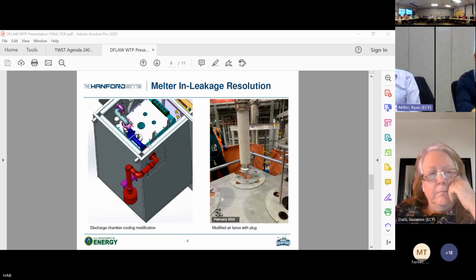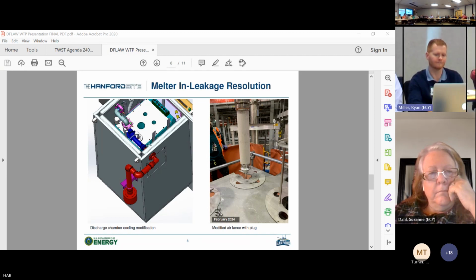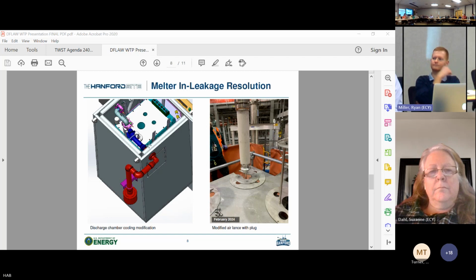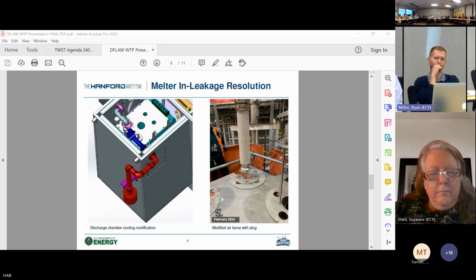The entire system, and I didn't highlight this, has a cascading ventilation system by law. You've got the gallery areas, the annulus area, and the plenum area. All of those are fully functioning. The only one that was in manual during this time frame was the off gas, which pulls the vacuum on the plenum. All the others have been operated in auto for months, so yes, they're all functional.